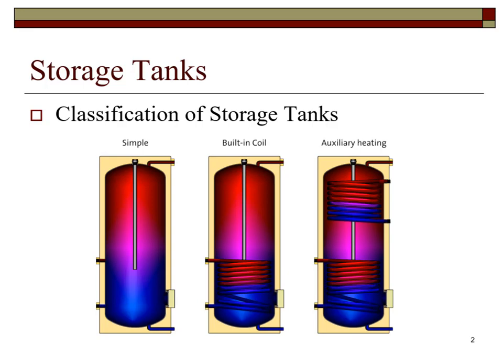There are a variety of hot water storage tanks, 3 of which are shown here. The tank on the left is a simple storage tank without a heat exchanger. Its function is simply to store hot water. The storage tank in the middle has a heat exchanger close to the bottom. This would be used in an indirect solar thermal hot water system.